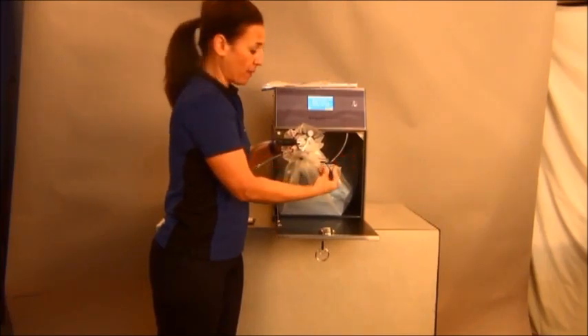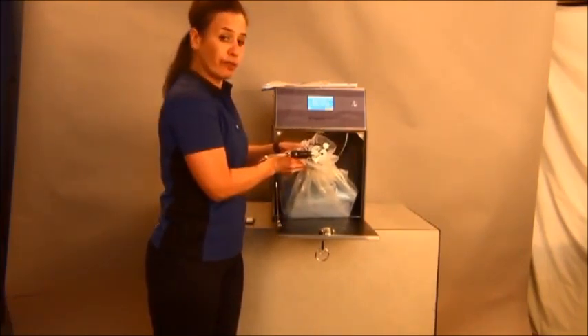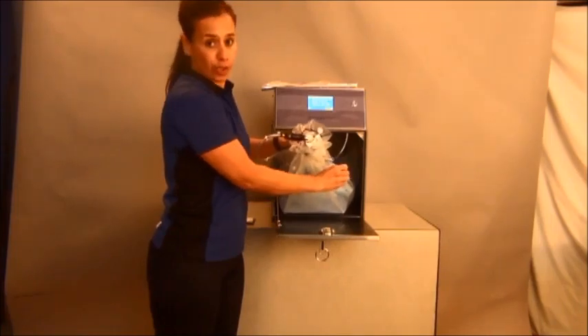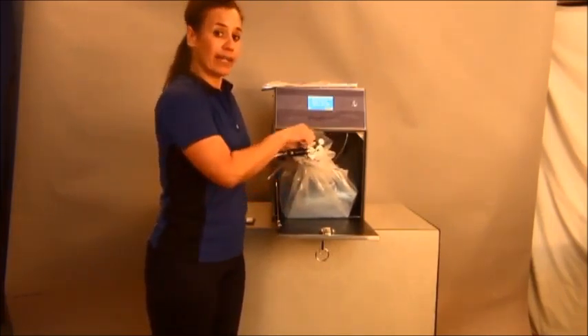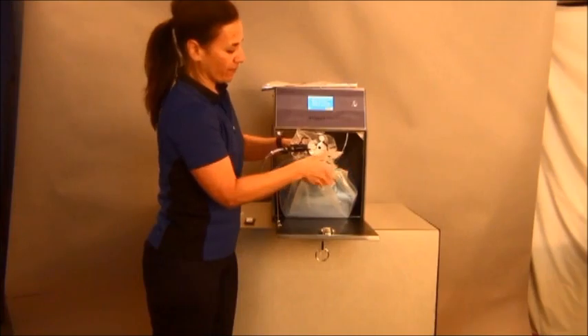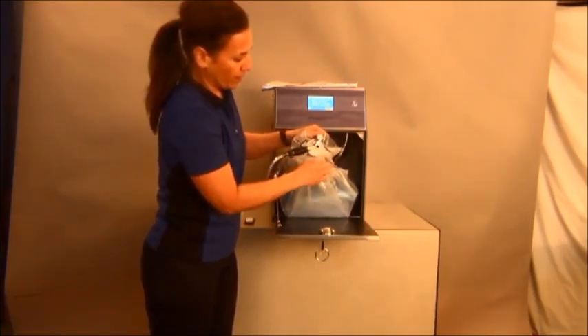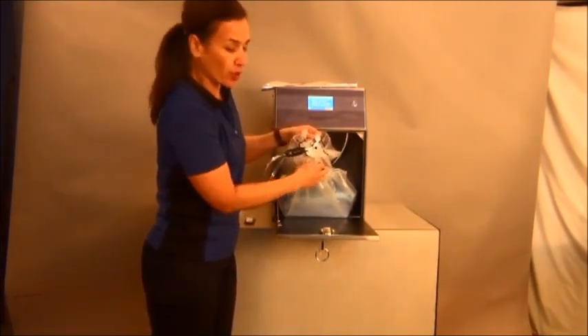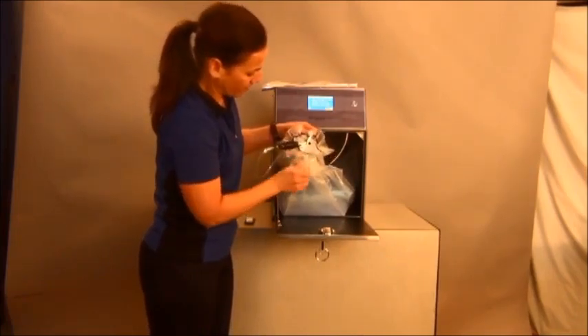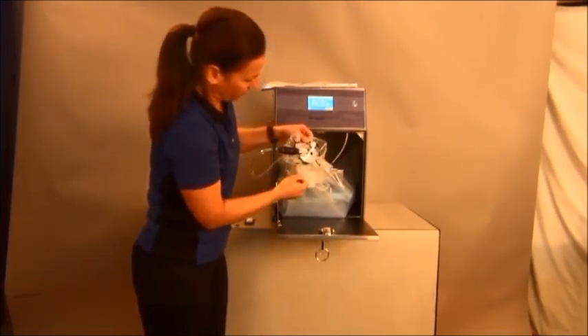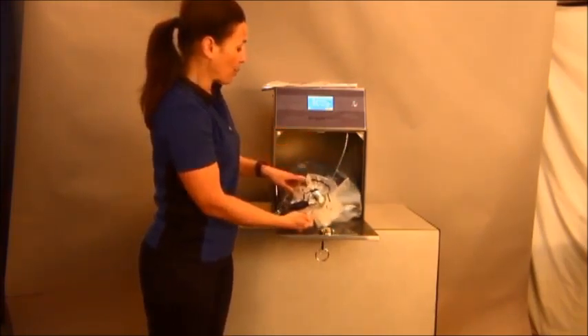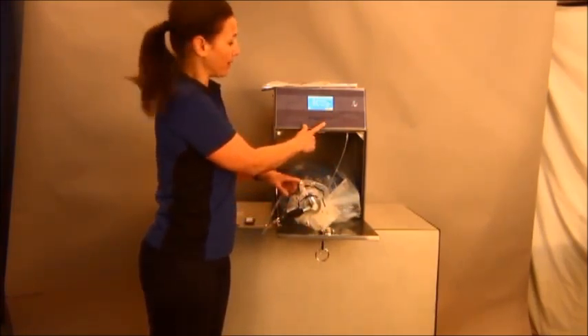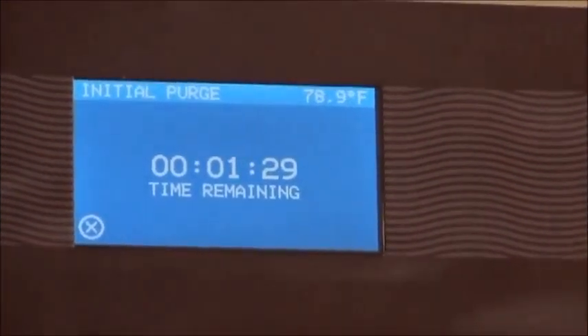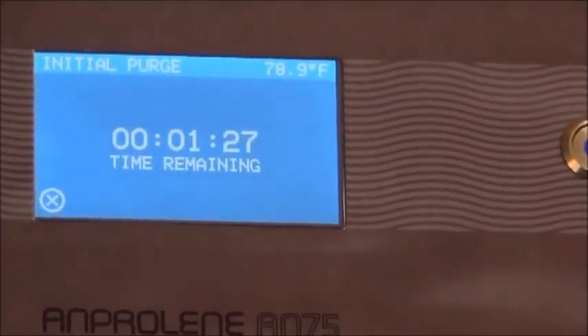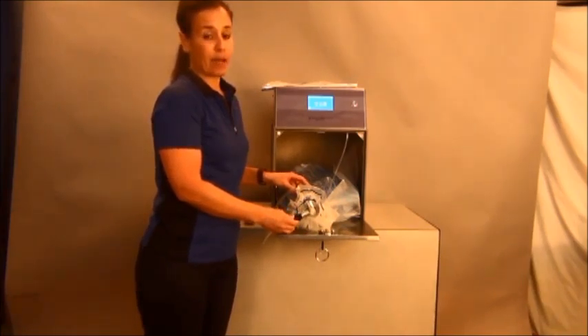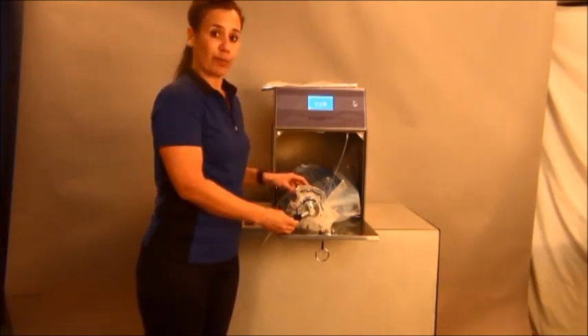Should at any point in time you need to remove items from your liner bag, you can do so. You have not as yet activated the cartridge. Pull the upper portions of your liner bag to make sure that there are no gaps. And at this point, you're ready to press the next button, which is purge. The purge cycle is 1 minute and 30 seconds, where it evacuates any dead or excess air from the liner bag.